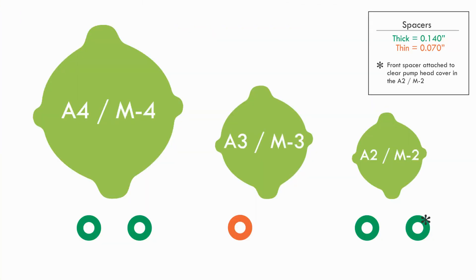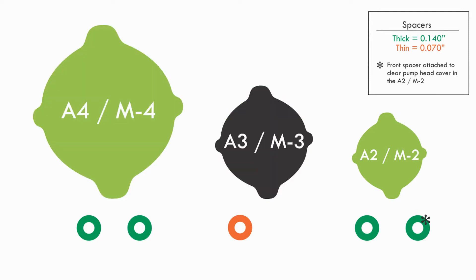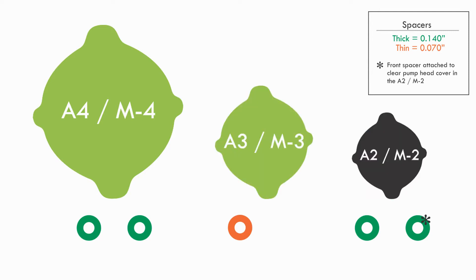First, let's break down which spacers are required for the three different FlexPro pump roller assemblies. The largest roller assembly requires one thick spacer in the front and one in the back. The medium size assembly for the A3 and M3 pump requires just one slim spacer in the back. The small A2 M2 pump requires the same as the A4 and M4 pump, one thick spacer in the front and one thick spacer in the back.